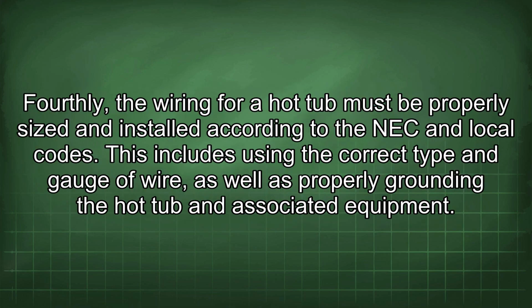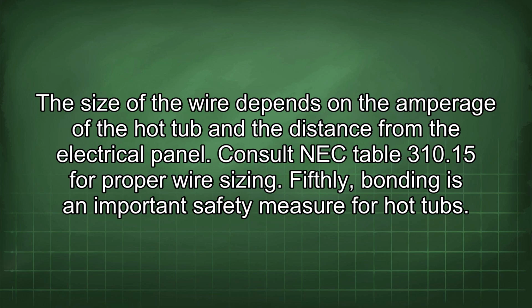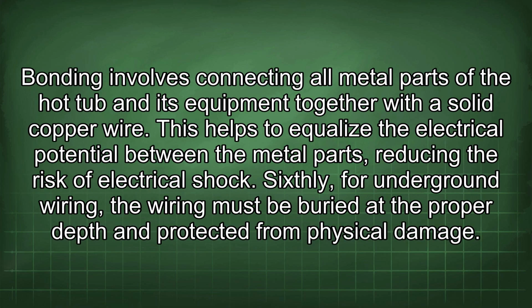Fourthly, the wiring for a hot tub must be properly sized and installed according to the NEC and local codes. This includes using the correct type and gauge of wire, as well as properly grounding the hot tub and associated equipment. The size of the wire depends on the amperage of the hot tub and the distance from the electrical panel. Consult NEC Table 310.15 for proper wire sizing. Fifthly, bonding is an important safety measure for hot tubs. Bonding involves connecting all metal parts of the hot tub and its equipment together with a solid copper wire. This helps to equalize the electrical potential between the metal parts, reducing the risk of electrical shock.